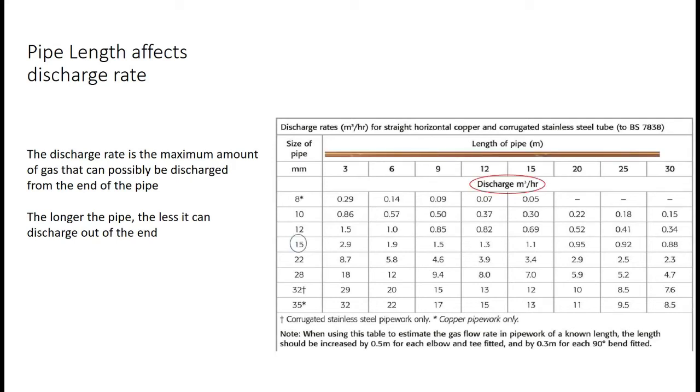For example, if we have a 15 millimetre pipe, if you have 3 metres of it, that can pass 2.9 metres cubed per hour of gas. But if you have 6 metres of it, it can only pass 1.9 metres cubed per hour.